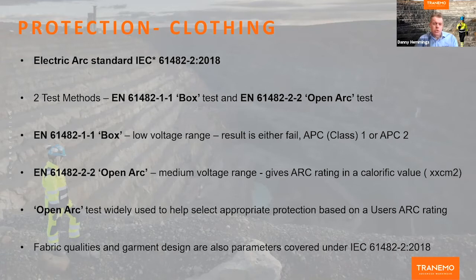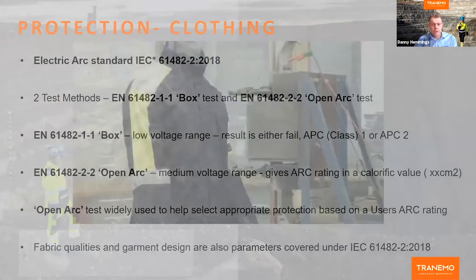So you have a situation where the standard has merged so that it creates these two tests in tandem. Most manufacturers will put garments through the box test and also through the open arc test. But it's widely recognized that open arc is better because it gives you an appropriate protection in calories per centimeter squared, which means you can apply that to your arc rating requirements. The other things that the standard covers are things like fabric qualities, garment design, functionality of garments. So there are other things that go within the standard.